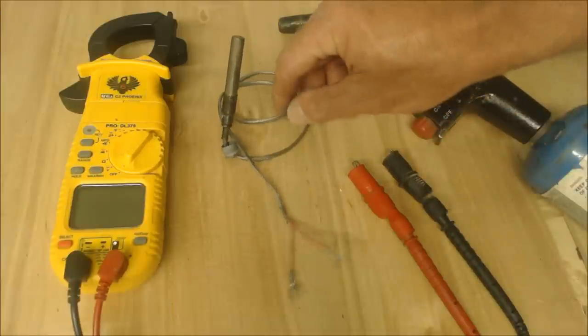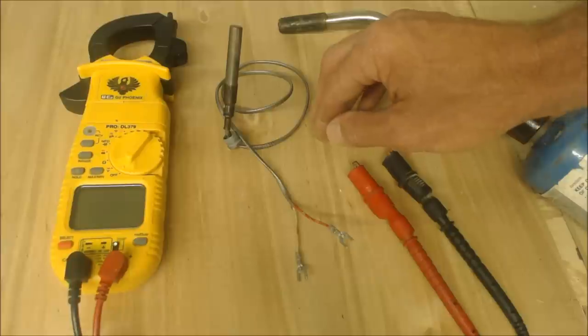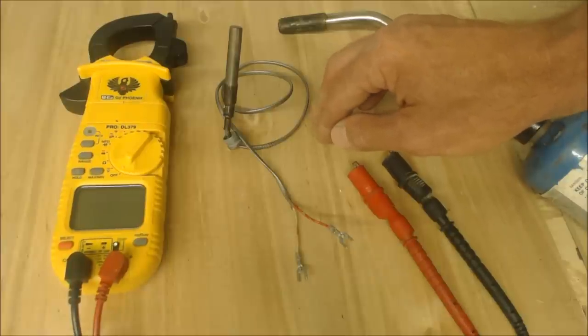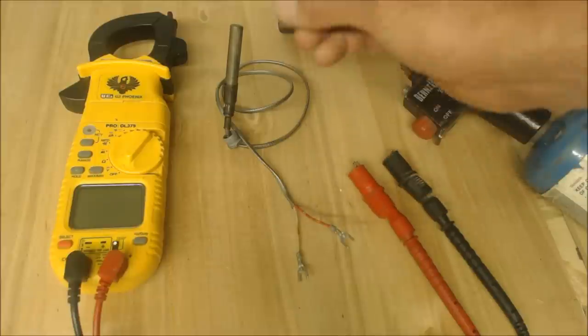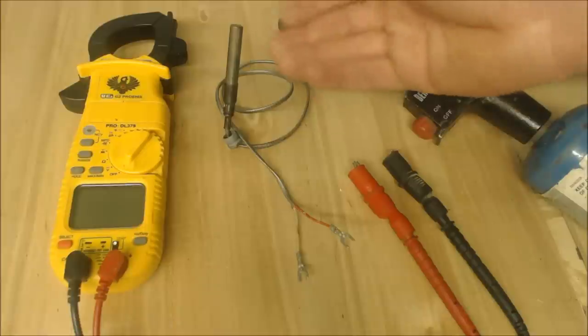What you're looking for is an open voltage of 350 to 850 millivolts DC. So this is open right now, and whatever your existing flame is, that's what you're working with, or if you can adjust it up a little bit.